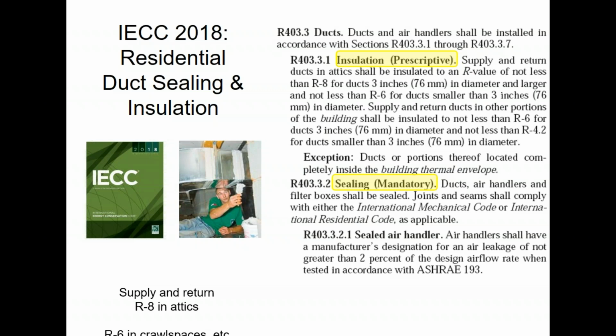If you have really, really small ducts under 3 inches, then you can see up top there the requirements are relaxed a little bit, because of the practicality of insulating really tiny ductwork, and the surface area doesn't have as much energy savings. In addition to ductwork being insulated, ductwork has to be sealed. Well, which ductwork has to be sealed? All ductwork has to be sealed. The whole entire project, you have to seal all of the ductwork. It is not optional. Specifically, ducts have to be sealed, air handlers have to be sealed, filter boxes have to be sealed. All the joints and seams have to be sealed and comply with the local mechanical codes. In the case of Indiana, the local mechanical code is the IRC, so it is in sync with this code.